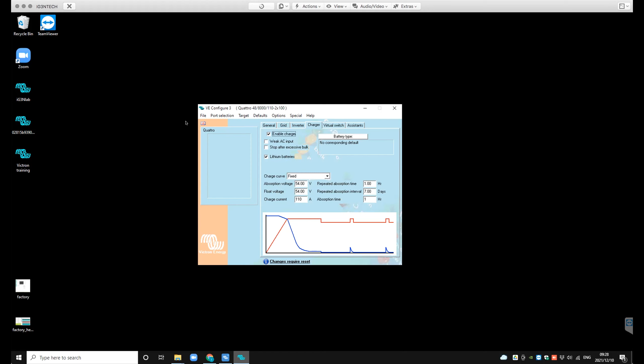We don't use any virtual switching, because if you have a virtual switch, you can't use ESS as an assistant. So let's just talk about assistants. ESS is basically an assistant that Victron brought out that incorporates Hub 1 and Hub 4. This allows you to manage your energy and where it's coming from, but it's only used with systems that are connected to the grid. So that will be in the hybrid system where you are connected to the grid and have a PV system also. And then this algorithm and ESS will help you to manage your energy via the GX device. And we can have a look at that a little bit later also.